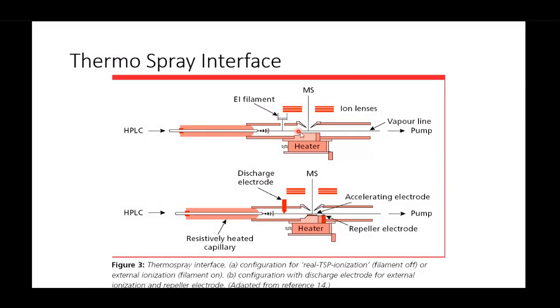Some sample molecules may enter the mass spectrometer, and most of the mobile phase will go here, that is what is expected, but a lot of mobile phase vapors also get into the mass spectrometer, giving you huge background and creating problems for the vacuum system of the mass analyzer. Because of that, this kind of interface never worked with very high sensitivity.